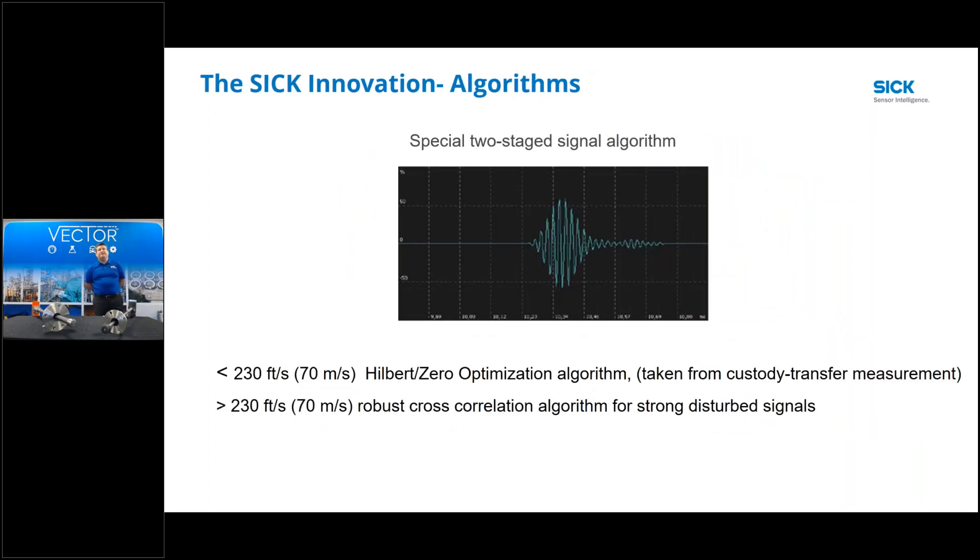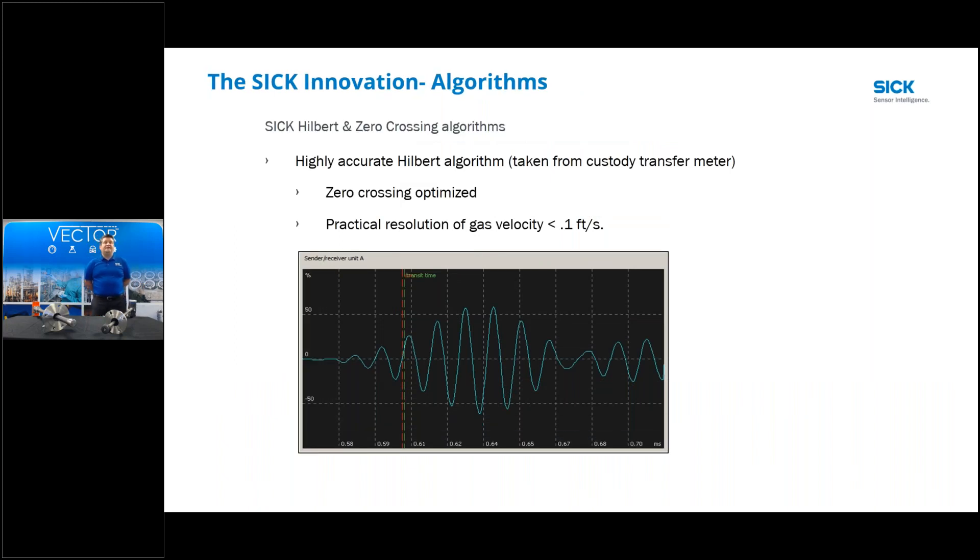On the low flow and high flow side, we have a special two-stage signal algorithm - one for low flow and one for high flow. They differentiate around 230 feet per second. The Hilbert algorithm, taken directly from our FLOWSIC600 custody transfer flow meter, is used in the low flow application. The other algorithm is the cross-correlation algorithm used for high flow. In the low flow measurement, we look at the third cycle peak-to-peak on the signal - not the whole signal, just one particular cycle.